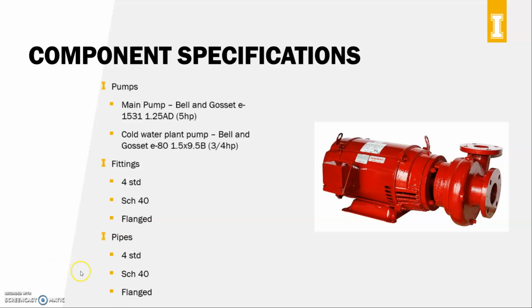Now, because of the pressure, we chose Schedule 40, and flanged, as it's stated in the write-up, it needs to be flanged if it's over 2.5 nominal, I believe. And also our fittings, of course, are just going to match our pipe system, so they're going to be 4 standard, Schedule 40, and flanged as well.